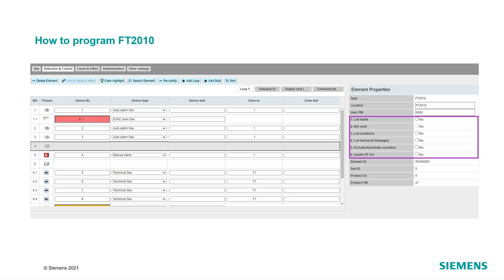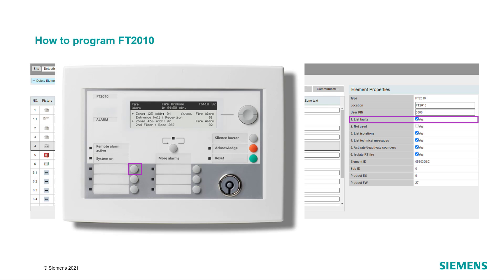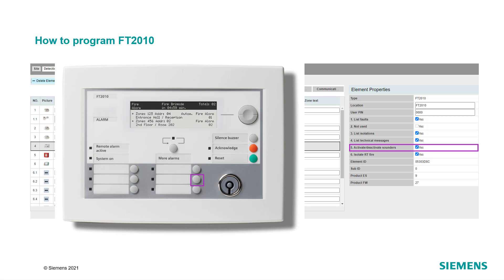For the FT2010, several functions can be added in the Element Properties tab. The function List Faults indicates all faults of the fire panel when the left top button of the FT2010 is pressed. List Isolations shows all isolations of the fire panel with the left button in the middle. The function List Technical Messages displays all technical messages with the top button on the right. With the function Activate/Deactivate Sounders, the user is able to deactivate or activate the sounders in case of an alarm when the right button in the middle is pressed.